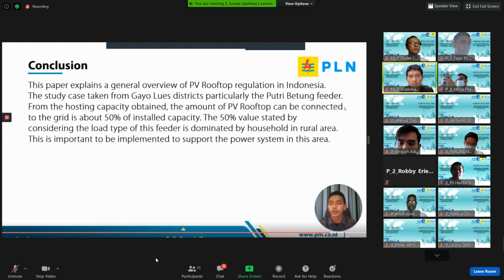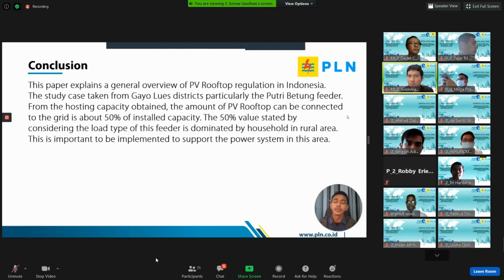So for the conclusion, I can describe that this paper explains a general overview of PV rooftop regulation in Indonesia. The study case is taken from Gayo Lues district, particularly the Putri Betung feeder. From the hosting capacity obtained, the amount of PV rooftop that can be connected to the grid is about 50% of installed capacity. The 50% value is stated by considering that the load type of this feeder is dominated by households in a rural area. And installing PV rooftop is important to support the power system in this area.